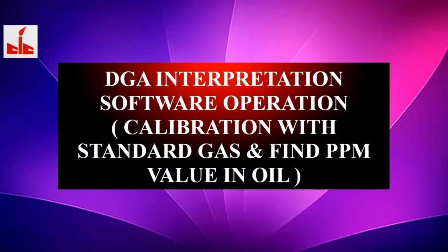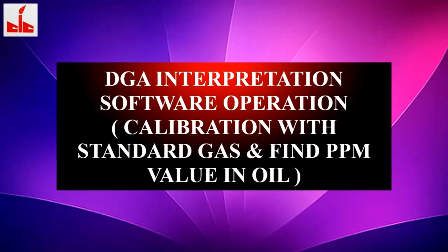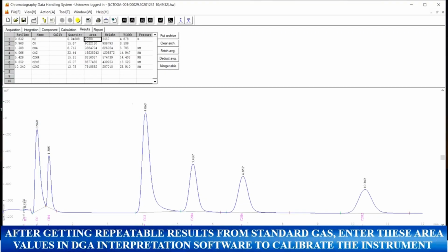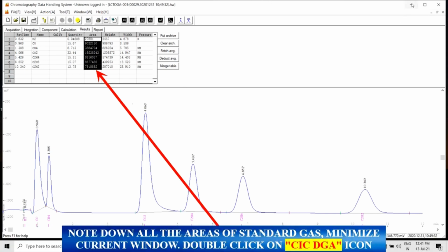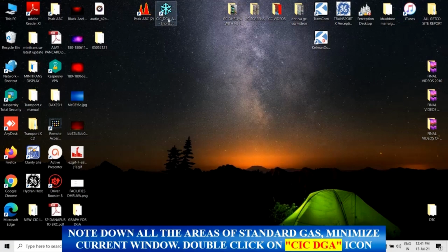DGA interpretation software operation: calibration with standard gas, and finding the ppm value in oil. After getting repeatable results from standard gas, enter these area values in the DGA interpretation software to calibrate the instrument. Note down all the areas of standard gas, and minimize the current window.